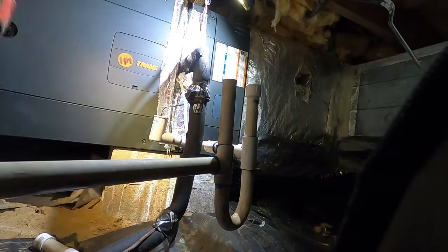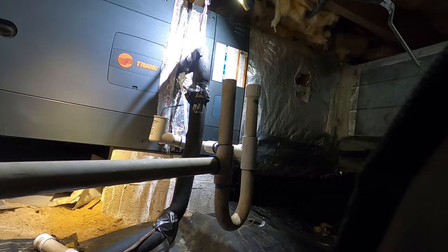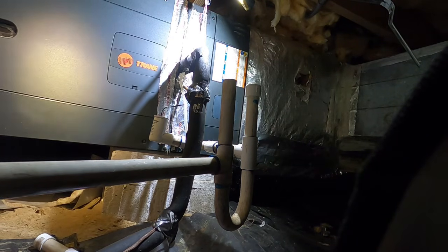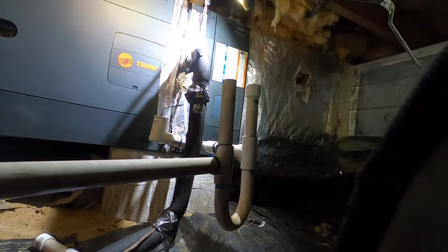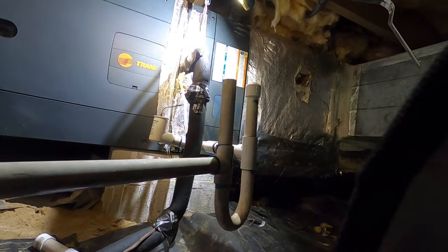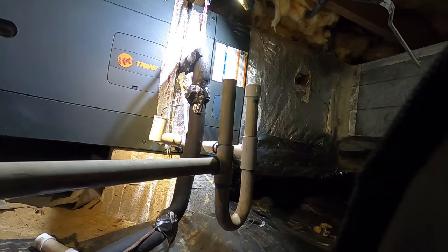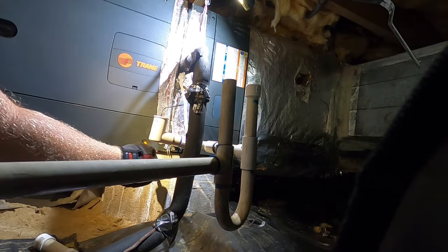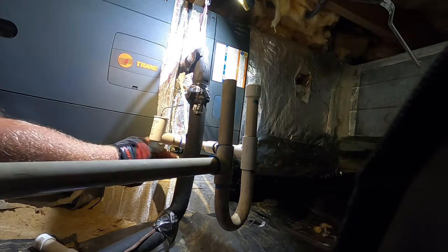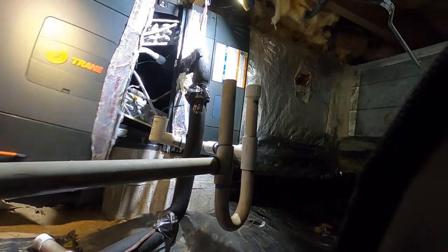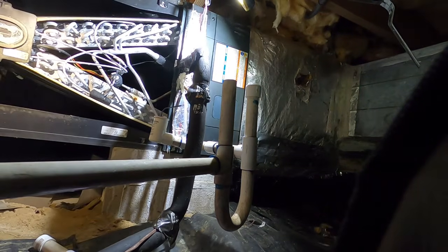let's open this thing up. Should be balanced, and that's why I say I'll turn the outdoor unit off. I'm going to let the air blow through this thing, and both my sensors should stable out to about the same temperature at that point after a few minutes. It's been about 10, 15, going on 15 by the time I get this door off. But I'll do this, and I test them by using the DC voltage.